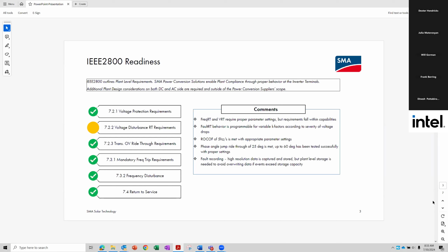The earlier requirement in IEEE 1547 was more about load rejection overvoltage. The emphasis was more on the inverter not causing an overvoltage. Here it is about grid events: capacitor switching events happen, fault clearing events happen, a transient overvoltage happens. A lot of inverters trip under these conditions.